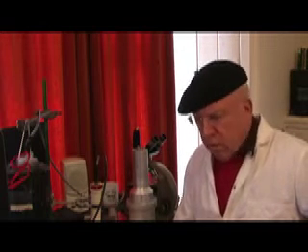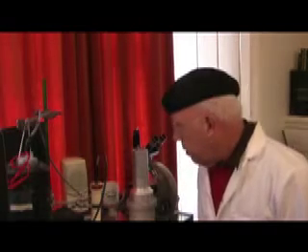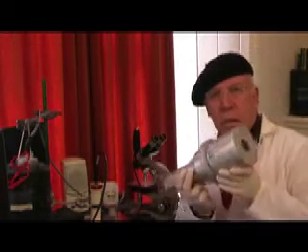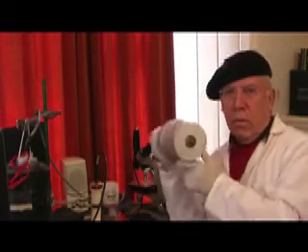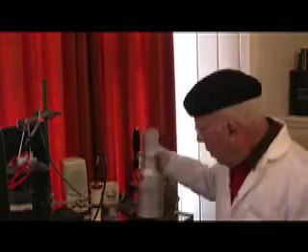what I was mostly interested in, first of all, was to use, we have a number of instruments here, but the first one to look at it with was a Geiger counter. So I looked through the package with a Geiger counter. It didn't look too bad. Didn't really look much above background. And we have some quite big, sophisticated gamma spectrometry equipment here. This is a large cesium iodide crystal. You put the sample in the hole. It's called a well detector, and then you measure the gamma radiation in there.